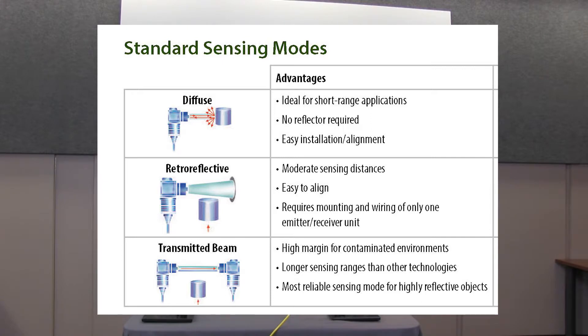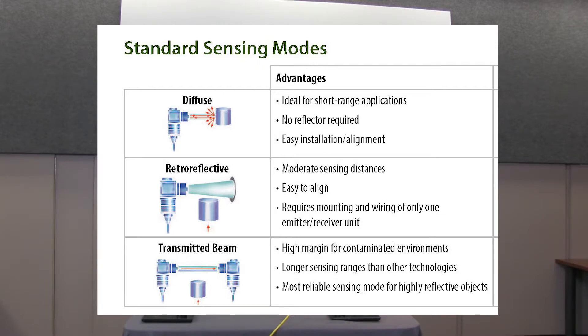The one you pick will be dependent on target, environment, cost, and performance. Transmitted beam sensors are capable of the longest sensing range. Retro-reflective sensors are capable of a long sensing range as well. Diffuse sensors are generally for close-in sensing because the sensing distance is determined a lot by the color and the shape of the object.